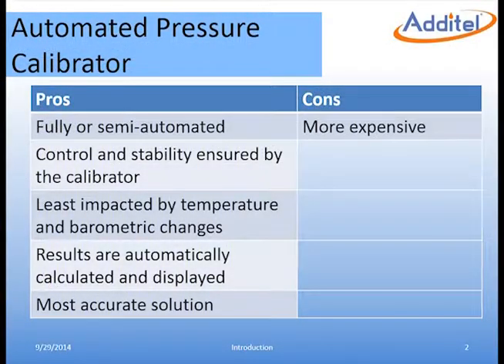Although the equipment used is more costly than the previous examples, this method can be fully or semi-automated depending on the DUT. Measurements are controlled and stability is ensured by the calibrator. The 761 is much less influenced by environmental changes than the previous example, and the results are automatically displayed and calculated. If you are calibrating a transmitter, the 761 is designed to fully automate the test by reading the electrical output of the transmitter and recording the pressure from the calibrator.